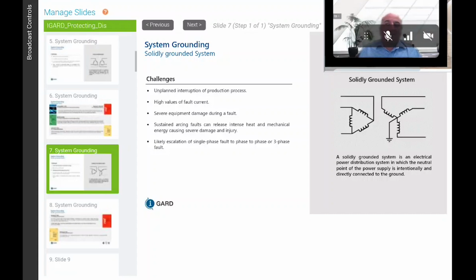Overcurrent protection does not work when you have a ground fault. You may not necessarily have sufficient current to trip the overcurrent device fast enough. The Canadian Electrical Code basically says that you have to trip in under 1 second, and I think the NEC has similar verbiage that says you have to trip relatively fast, because you want to stop the current flowing to prevent fires. You have high current values, severe damage. Basically, if you have a solidly grounded system, you can have anywhere from 10,000 amps to 50,000 amps flowing in that ground fault circuit.